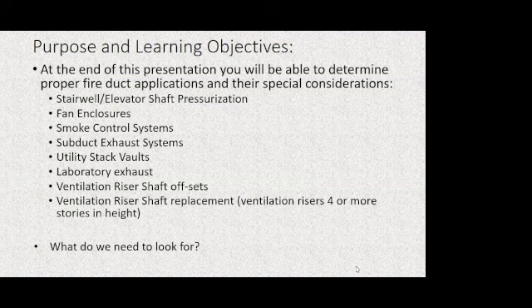And of course, there are now products that actually are legitimately replacing the shaft itself with a fire rated duct product. And the reason I'm going to home in here on the criteria that says 4 or more stories is because that's what triggers that 2-hour fire resistance rating. Below that, it's only 1 hour, and if you're only penetrating one floor, of course, you can use a fire damper. That 2-hour threshold is extremely important. We're going to talk about why.